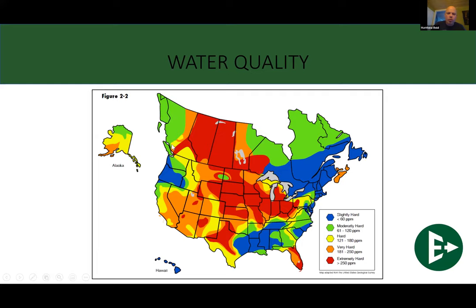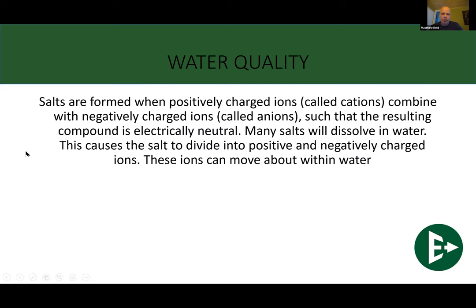Now, this is a map of the approximate water quality in Canada. With the exception of the tip of Southwest Ontario, Ontario, Quebec, Newfoundland, and some of the Atlantic provinces have relatively decent water. But once we get into Manitoba, Saskatchewan, Alberta, and BC, we start getting into some not great water, and we get quite hard water out there. So we need to be cognizant of this and start working with it, because as that hard water is there, these salts are now embedded in this water. They've dissolved in this water. Now, the salts will eventually come out of solution. Whether that water is heated or cooled depends on what salts come out of solution.